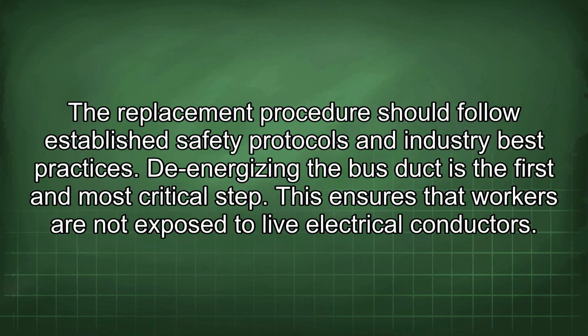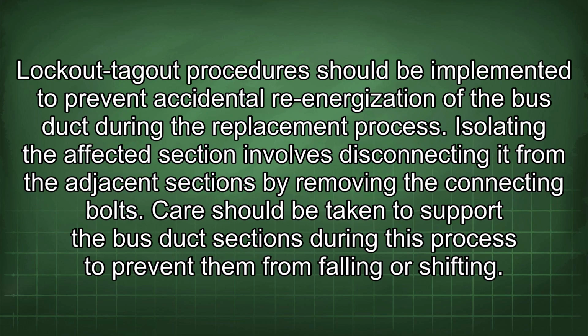The replacement procedure should follow established safety protocols and industry best practices. De-energizing the bus duct is the first and most critical step. This ensures that workers are not exposed to live electrical conductors. Lockout-tagout procedures should be implemented to prevent accidental re-energization of the bus duct during the replacement process. Isolating the affected section involves disconnecting it from the adjacent sections by removing the connecting bolt. Care should be taken to support the bus duct sections during this process to prevent them from falling or shifting.